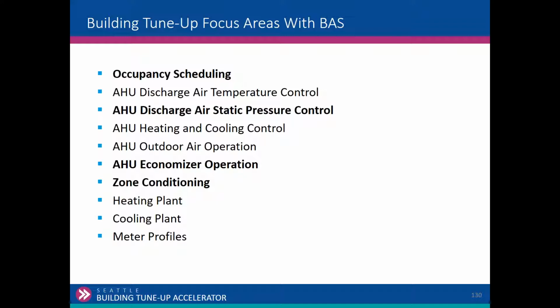And zone conditioning, which is essentially set points. I'll talk a little bit about this. You may have a wild zone or rogue zone. You may have a data closet on a VAV system that isn't allowing the discharge air to be reset, because that VAV box is 100% open 24/7. Has anybody seen that before? So you have reset capability, but you have one zone that's driving the entire system. That may be a recommendation to upsize the VAV box or put in a separate system. That's outside the scope, but it's something that we want to know in your analysis, that we can't do any reset because all the air is being demanded by the one zone. So that's a recommendation. Heating and cooling plants we'll talk about a little bit later.